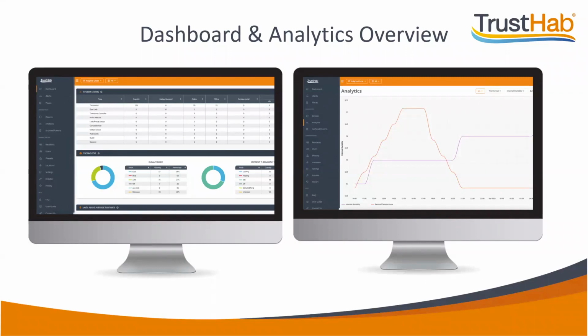The best example of potential cost savings is locating and remedying units that are running excessively. The initial 24 hours after install shows you which units struggle to reach their set points, if they reach them at all. Those units have likely been running like that for months, if not longer. You'll be able to easily see your property and building runtime averages, so you can locate the units which are outliers and likely provide them maintenance.